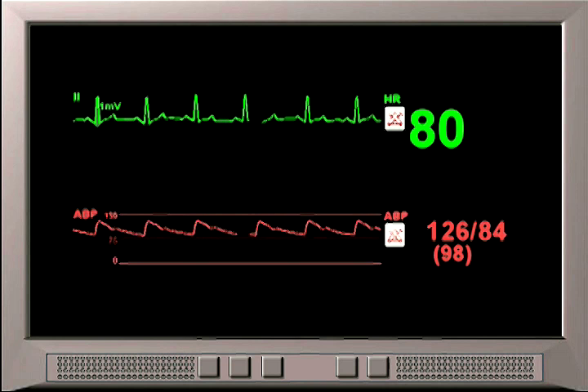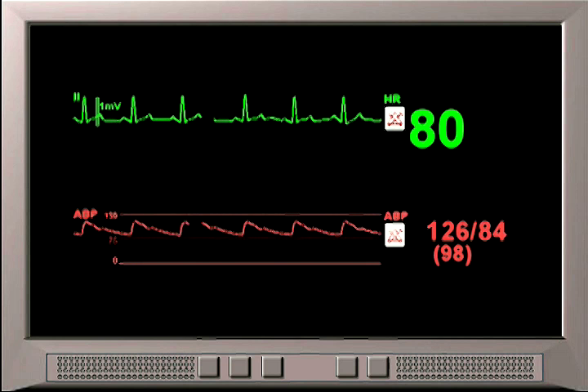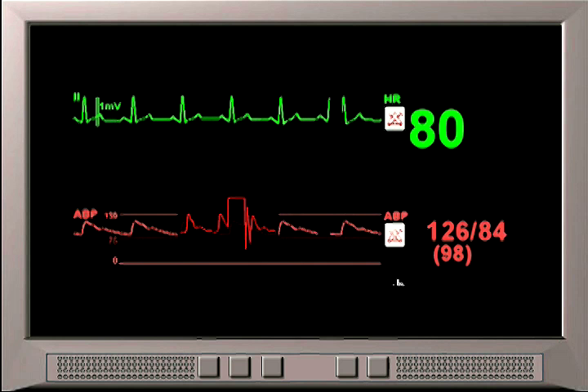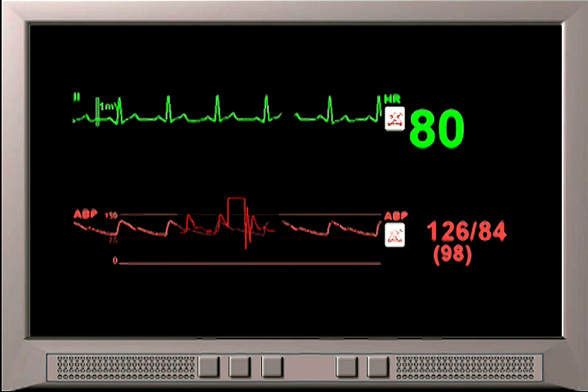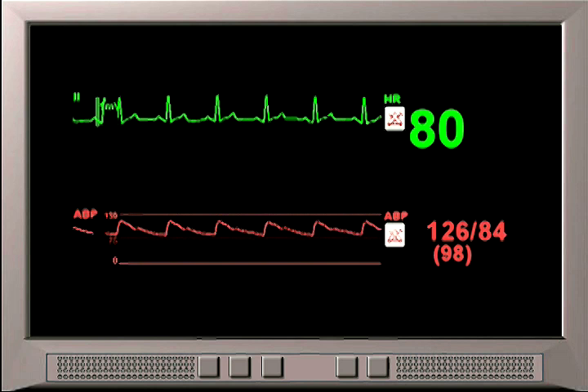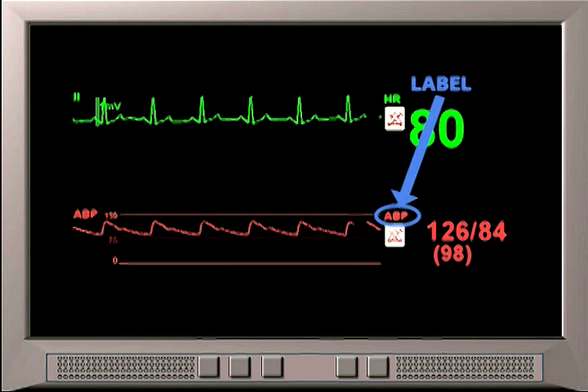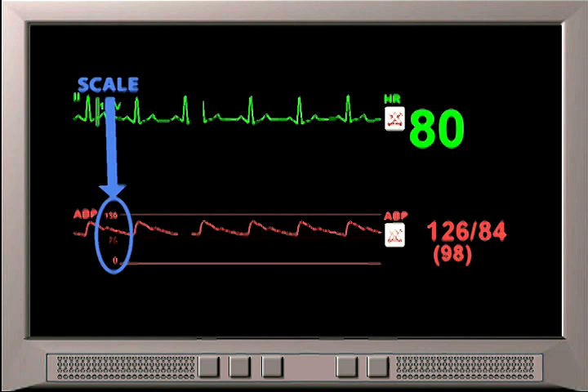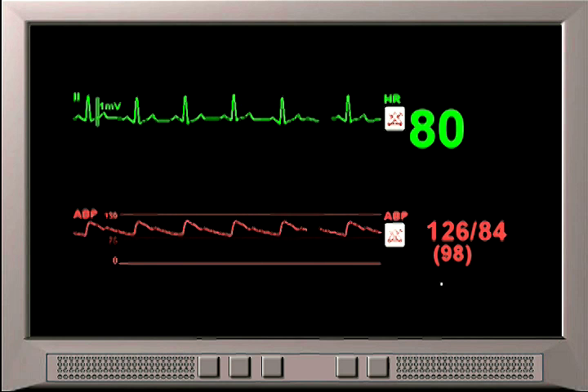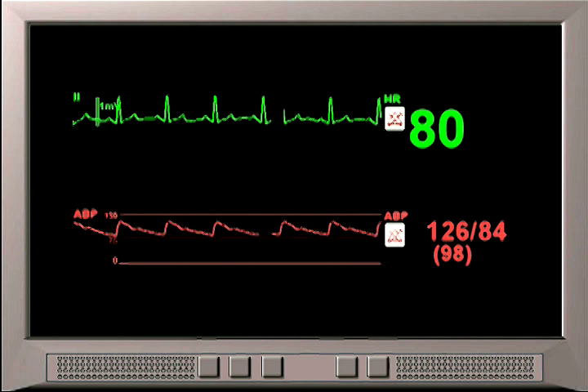Step 7. Confirm the appropriate pressure waveform and numeric values are present. Perform a square wave test to assess the frequency response of the system. Confirm the pressure channel has the appropriate label, scale, alarm settings, and color coding for the physiologic pressure being measured.